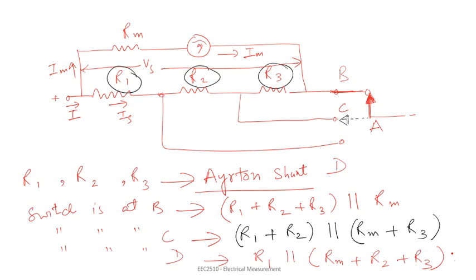Because the shunts are permanently connected and the switch makes contact with the shunt junctions, this instrument is never left without a parallel connected shunt. Understand? This is a necessity in this type of instrument, because in any situation the instrument should not be left without a shunt in the circuit. In that situation a current will flow in the moving coil that will be large enough to destroy the instrument.